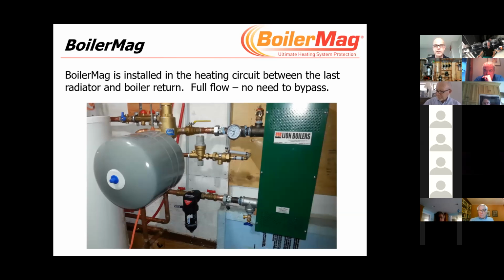We always try to say full flow and there's no need to bypass, but the reality is some boiler rooms are packed with pipe work. We haven't always got access to it. We've got to put it wherever it's most appropriate. It could be that the customer can't afford to invest in the massive system, but they can afford to put it on a side stream or a bypass. Honestly, I'd take that. If you're going to put a BoilerMag on there and you can only afford a 2-inch, a 4-inch would be better. I'll take you putting the 2-inch in rather than putting nothing in at all.